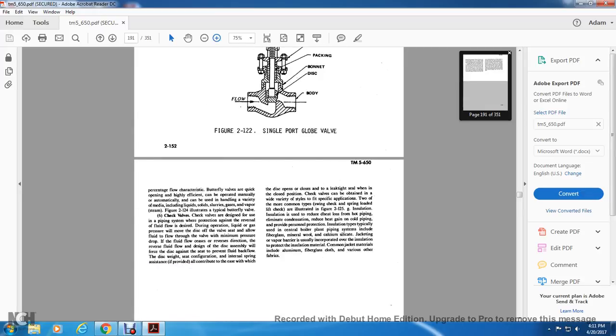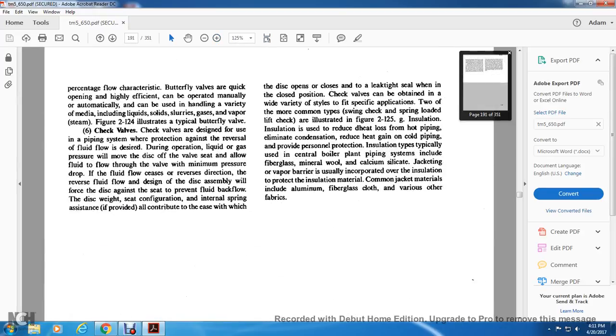And then we return to the check valves. Check valves are designed for piping systems where protection against reversal of fluid flow is desired. During operation, liquid or gas pressure will move the disc off the valve seat, allowing fluid flow with minimum pressure drop. When the fluid flow reverses, the design of the disc assembly forces the disc against the seat, preventing fluid backflow. The weight, seat configuration, and internal spring resistance all contribute to the ease with which the disc opens and closes, and to leak tightness when closed. Check valves can be obtained in a wide variety of styles to fit specific applications. Two of the more common types are the swing check and the spring-loaded lift check, also illustrated in Figure 2-125.